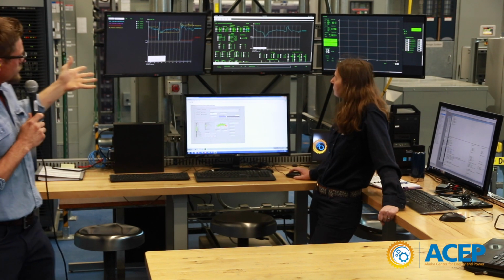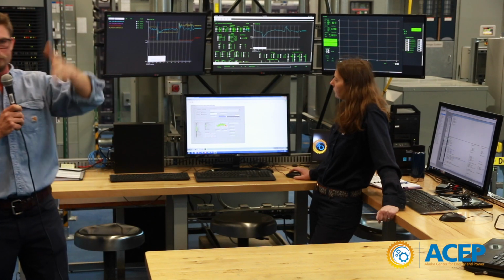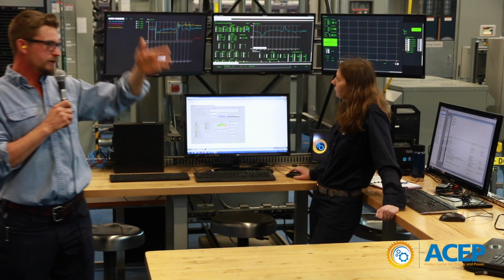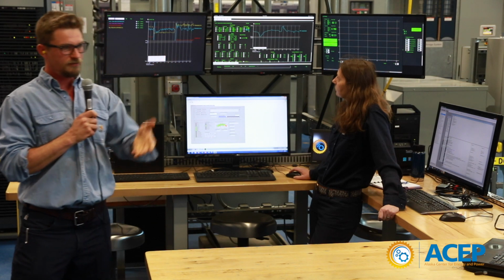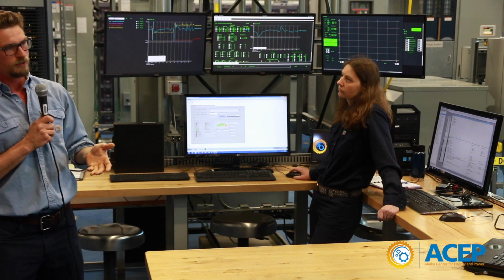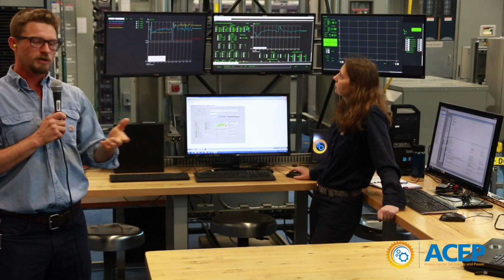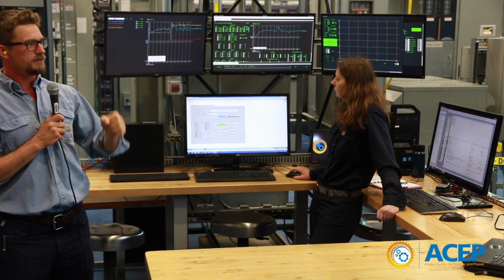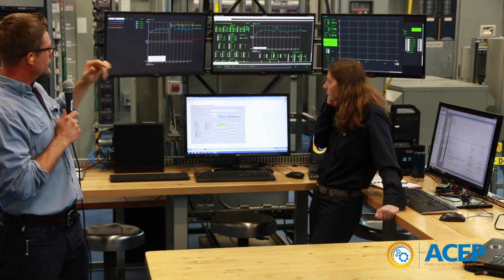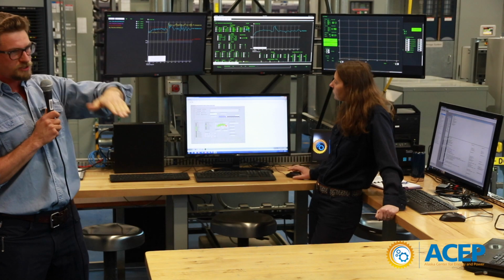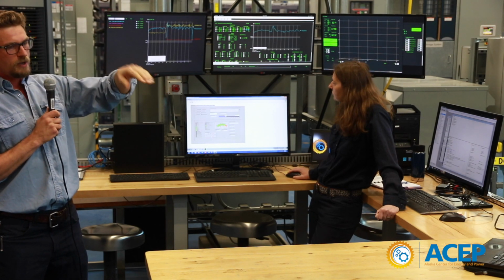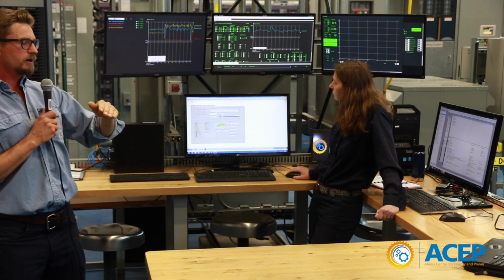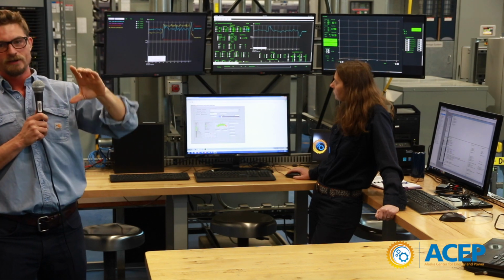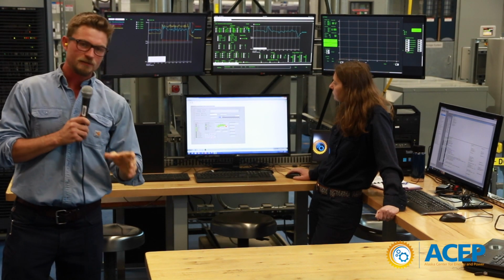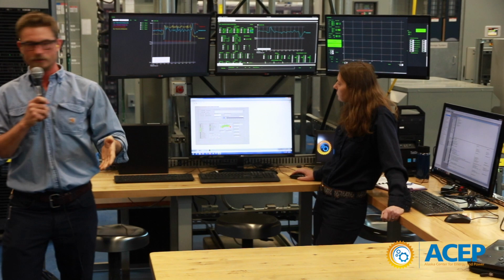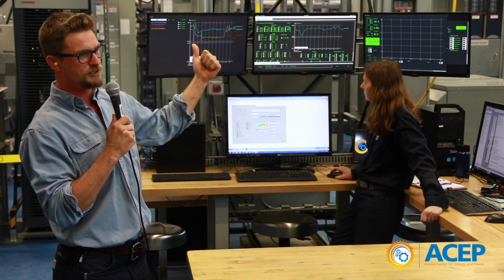Remember, our system load kind of goes around 150, and we've had 50 kilowatts of wind power installed, so we don't have to curtail wind that often. Sometimes if it's a windy night and our load goes down to around 50, we have to curtail some of our wind power because we need to keep the generator online. We can't turn our generator off yet, right? There will still be 50 kilowatts of wind power.